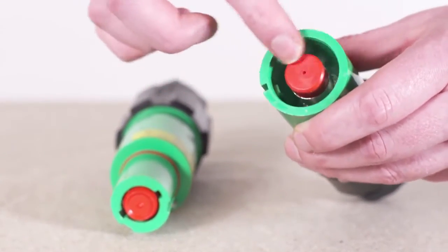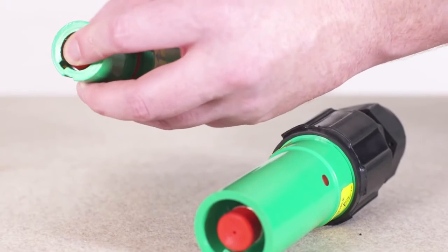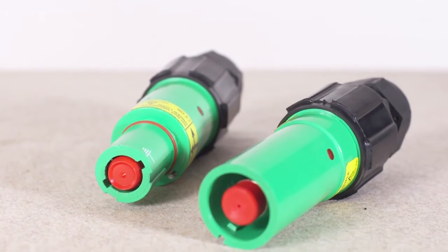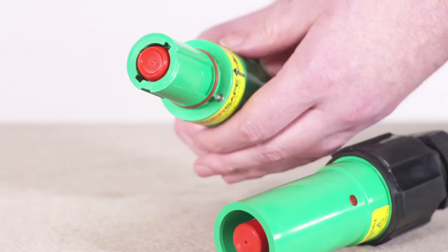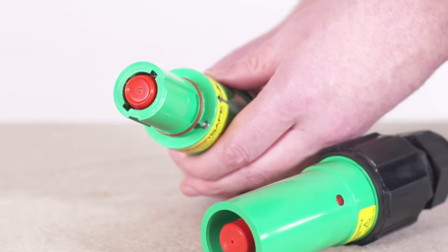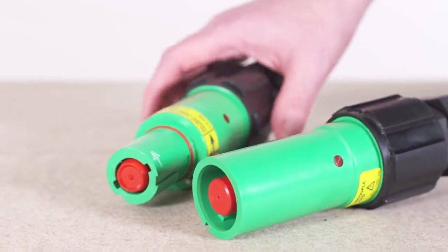This does not, however, compromise safety because the gap between the plastic insulating cap on the male pin of the source connector and the surrounding plastic housing is too small to insert a human finger. The female drain connector also has a spring-loaded plastic cap to prevent casual contact with the electrical contact.